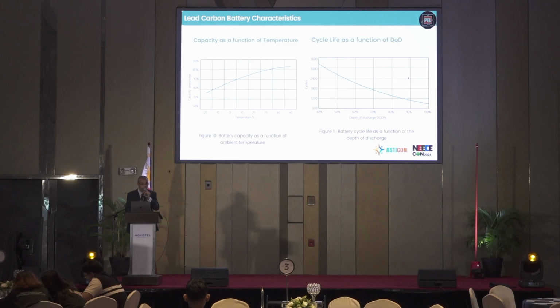So 70% DOD means you can discharge it way further than the lead acid, and it is very close to the recommended operating mode of the lithium. But if you look at the performance, here at 100% DOD, you can still get around 800 or maybe 900 cycles, which is way better than what you would get in lead acid. This is already close, well, not really close, but nearer to the performance of lithium. It's farther away from lead acid.